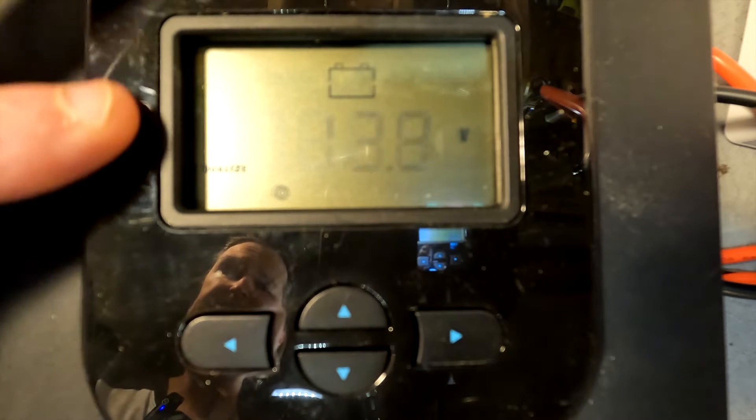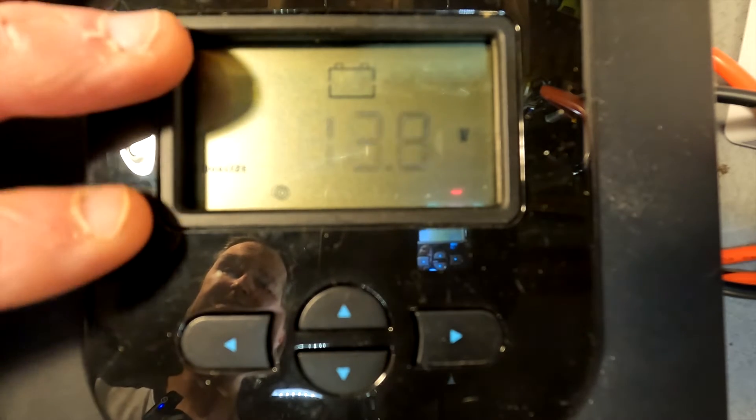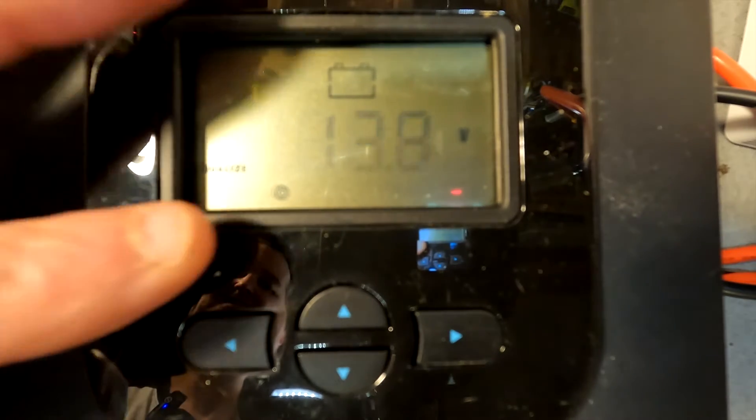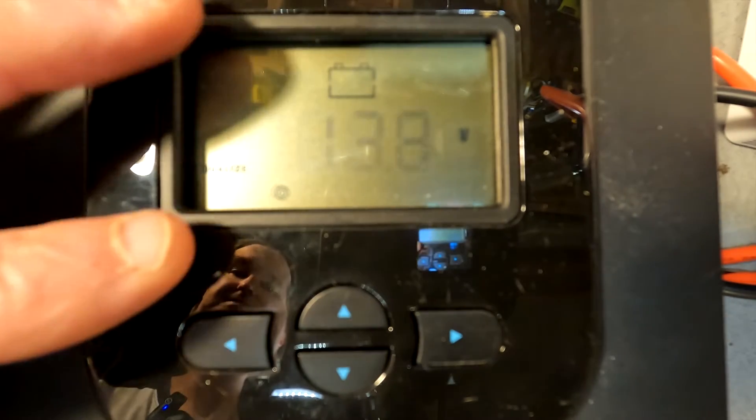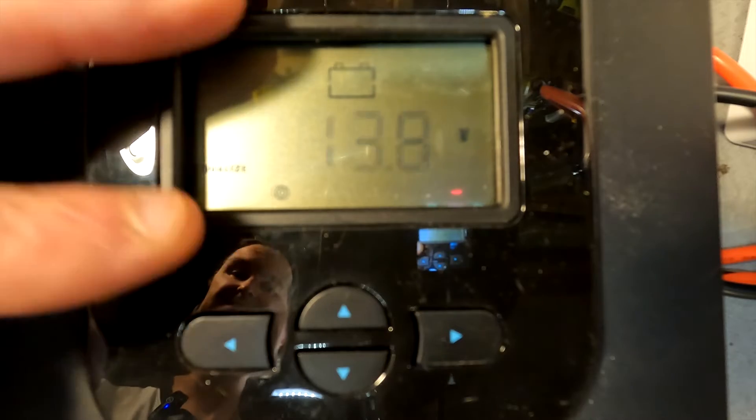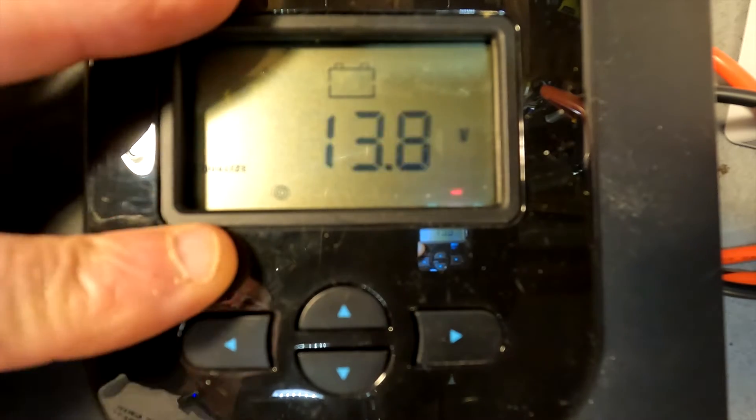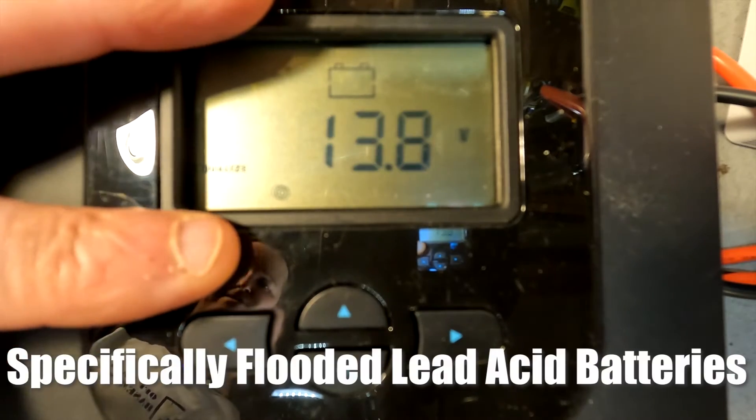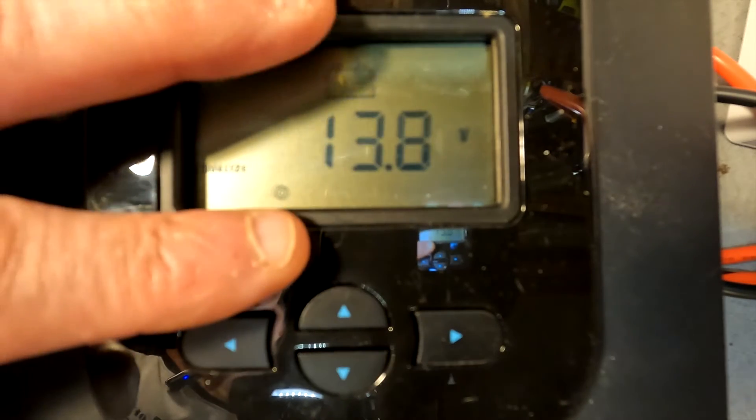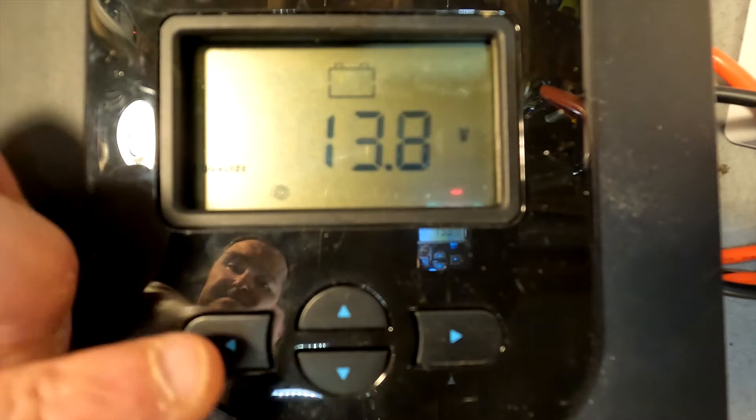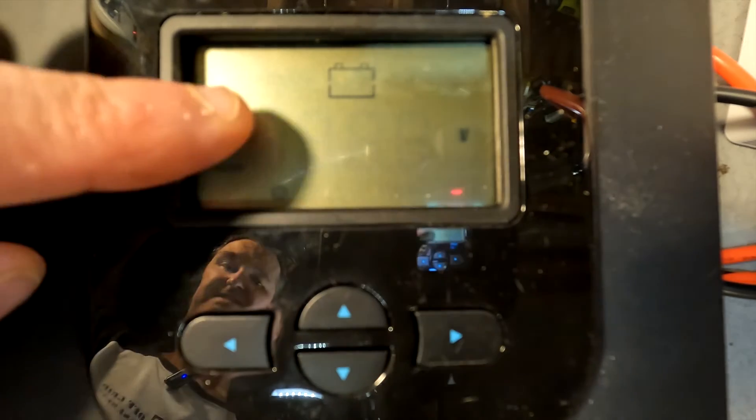Alright, and the first thing is the equalization. For lithium iron phosphate you don't need to do anything with equalization. That's for lead acid batteries. So we're going to go ahead and keep that at 13.8, which is the same voltage as the float setting.